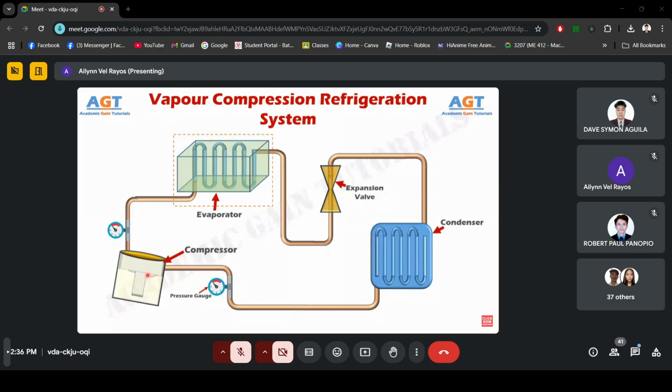First of all, the compressor starts working. The job of the compressor is to pressurize or compress the vapor refrigerant inside the compressor chamber. Here, in the vapor compression refrigeration system we commonly use either ammonia or freon as a heat-carrying medium throughout the whole procedure. Now, we know that if pressure increases, it also increases the temperature. So, when this vapor refrigerant is compressed inside the compressor chamber by squeezing the vapor very tightly together, it will heat up. After that, this high pressure and high temperature vapor refrigerant will leave the compressor and enter into the condenser through the connected pipe.